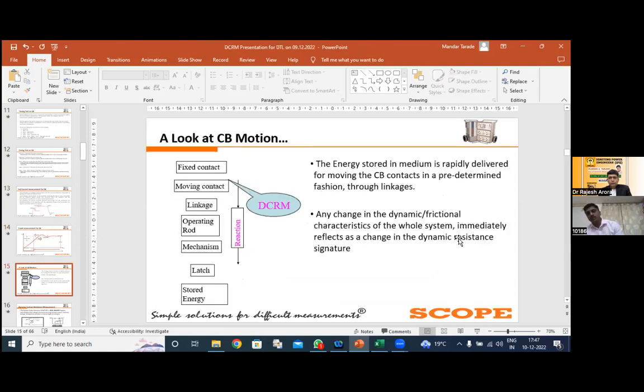Moving ahead, have a look at the circuit breaker motion. There is the fixed contact. Next one is the moving contact. Linkages are there, the operating rod is there, the mechanism is there, the latch is there, and stored energy is there. As all of us know, the energy stored in the mechanism is rapidly delivered for moving the CB contacts.